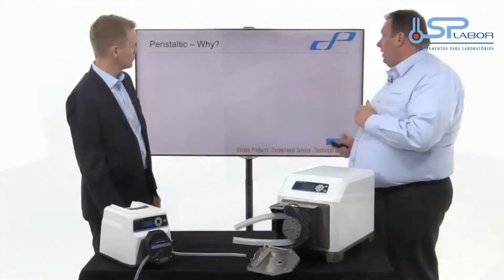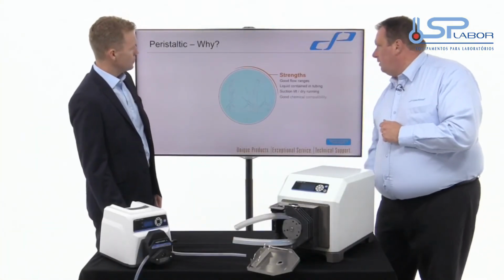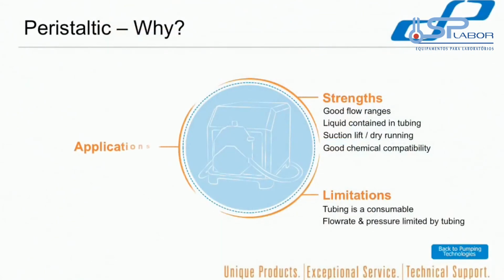Yes. If we were to summarise them, the strengths are, as a positive displacement pump, a very good flow range, and the liquid containment within the tube. The tube is the pump, the liquid chamber, the seamlessness of the chamber. These are strengths I can't emphasise enough. They can suction lift and they can dry run. A suction lift is to lift the liquid from a height, and these do a very good suction lift. If you put your cup of tea out the window, down at ground level, and we're on the first level, you could drop the tube into the cup and suck your tea up from ground level to your desk. It's that sort of suction lift we can offer.